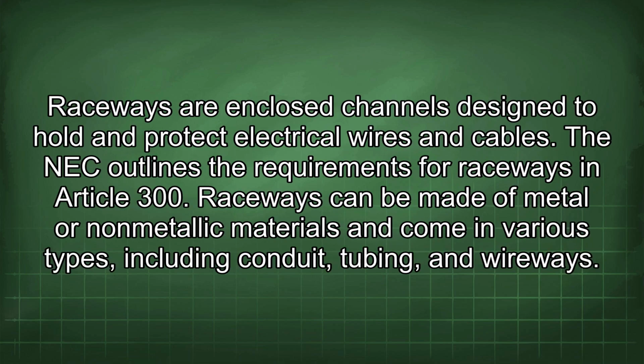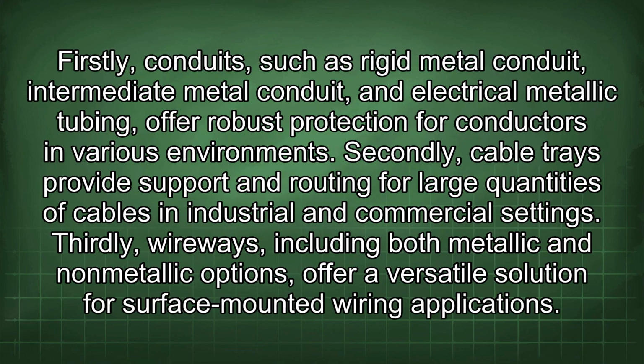Raceways are enclosed channels designed to hold and protect electrical wires and cables. The NEC outlines the requirements for raceways in Article 300. Raceways can be made of metal or non-metallic materials and come in various types, including conduit, tubing, and wireways. Firstly, conduits, such as rigid metal conduit, intermediate metal conduit, and electrical metallic tubing, offer robust protection for conductors in various environments. Secondly, cable trays provide support and routing for large quantities of cables in industrial and commercial settings. Thirdly, wireways, including both metallic and non-metallic options, offer a versatile solution for surface-mounted wiring applications.